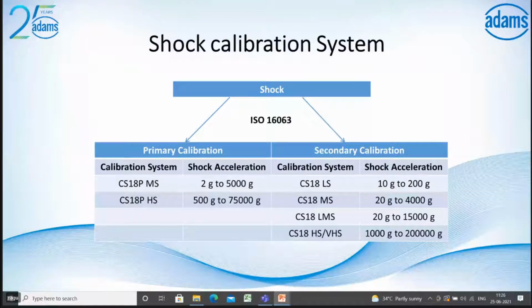And the shock calibration system. This is based on the standard ISO 16063, the method for the calibration of shock transducers. Spectra is offering primary and secondary calibration. The primary calibration is the CS18P medium shock, with maximum acceleration up to 5000 G, and the CS18P HS, that's a high shock, with maximum acceleration up to 75,000 G.